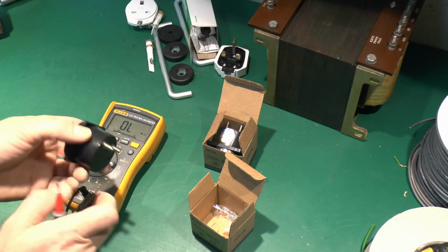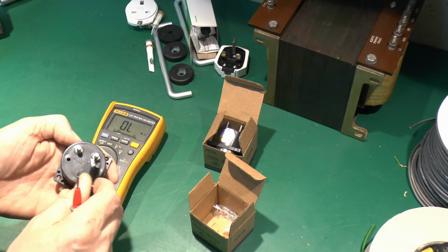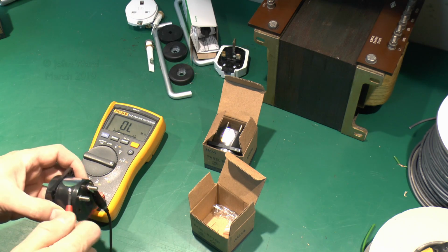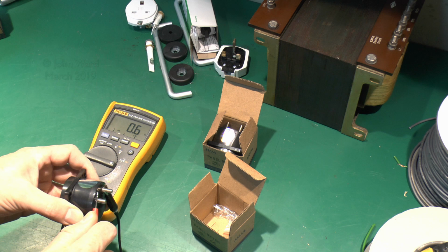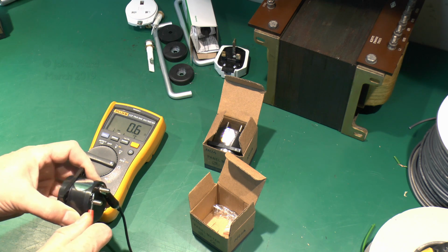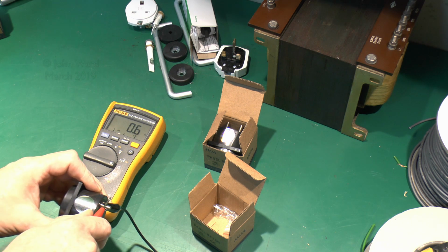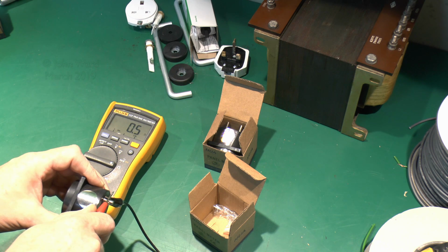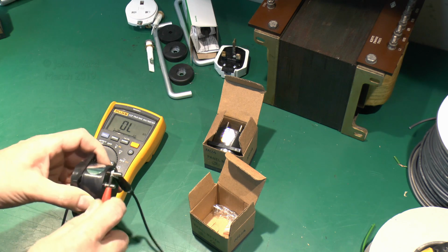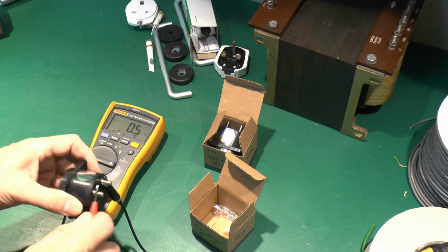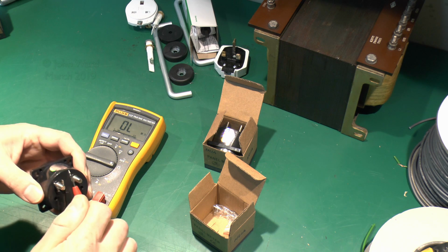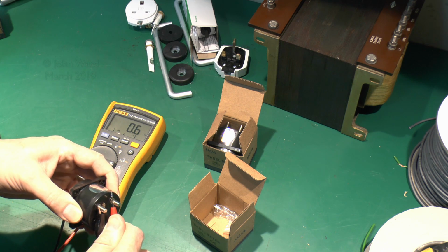Again, these are marked plus and minus, but let's try the proper way round, and we should get extremely low resistance, so 0.6 ohms. Let's check what the leads measure: 0.6 ohms, 0.5, so we're looking at around 0.1 ohms for the meter itself. Again, that's perfectly reasonable, basically we want it to be as close to 0 as possible.